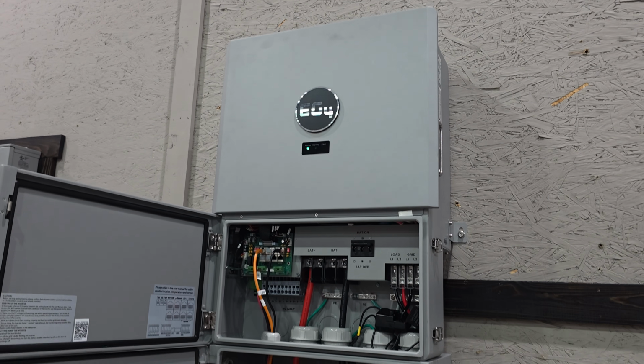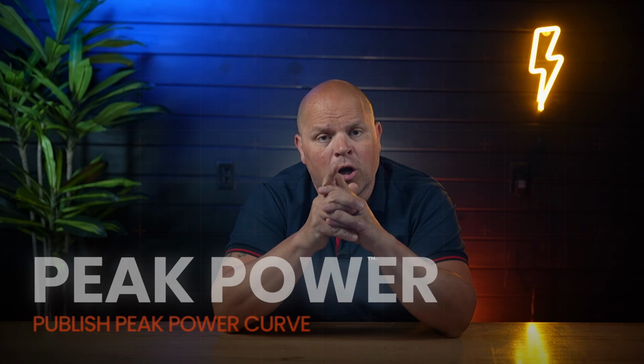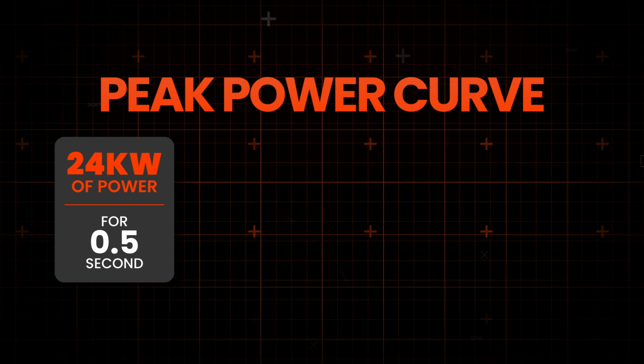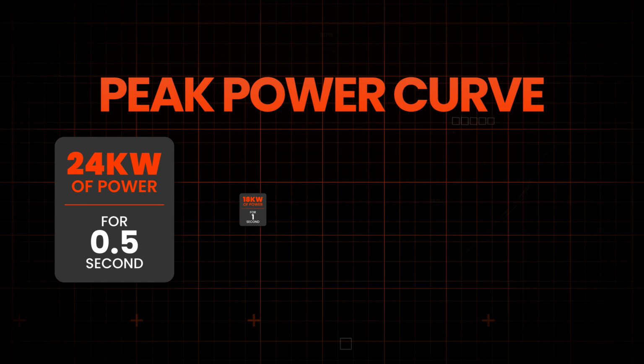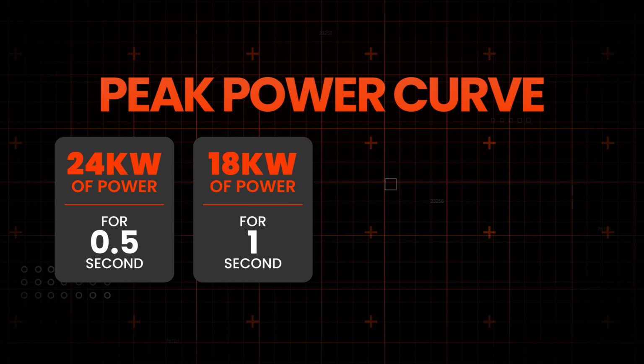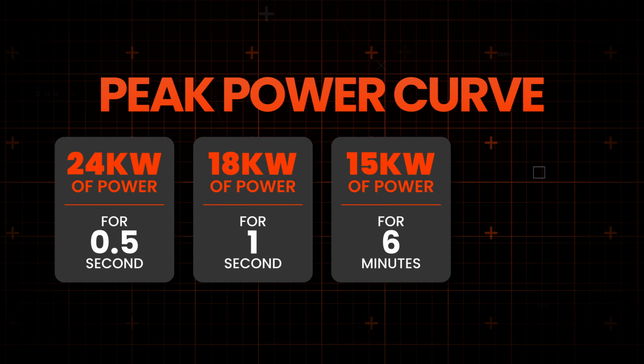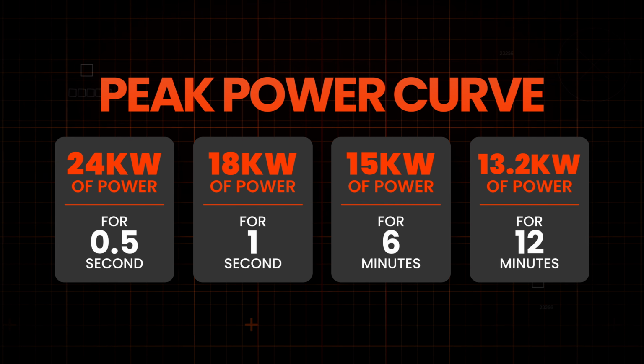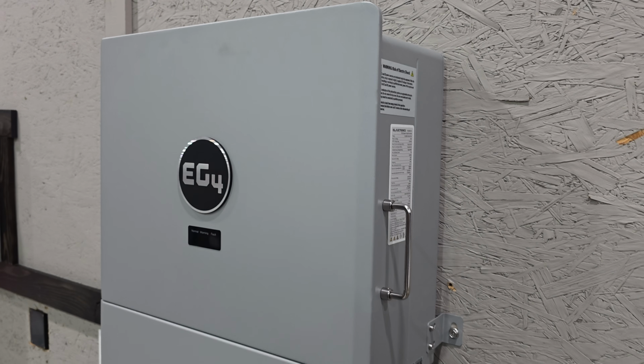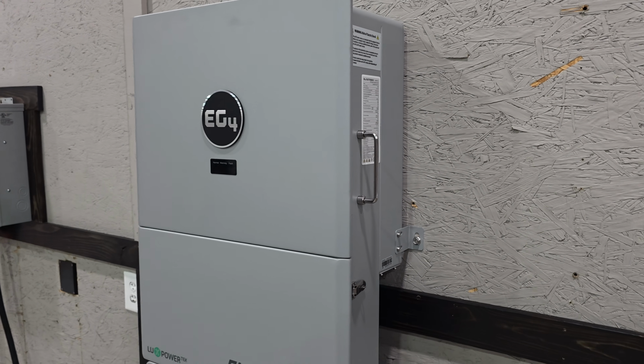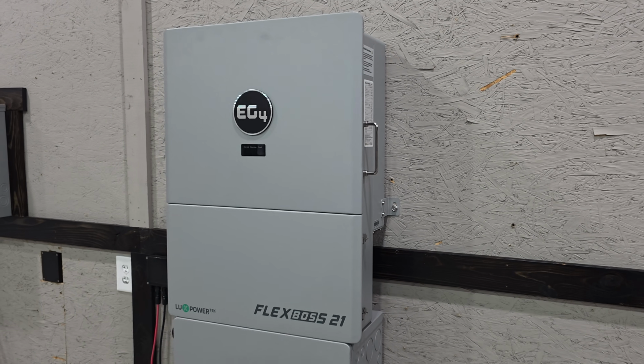The EG4 FlexBOSS 21 also gives you a published peak power curve: 24 kilowatts of power for half a second, 18 kilowatts for 1 second, 15 kilowatts for 6 minutes, and 13.2 kilowatts for 12 minutes. That kind of detail is very helpful because it gives you a better picture of what the inverter can handle during short spikes in your loads. So from a power perspective, this is one of the first reasons I think the price makes a lot of sense.